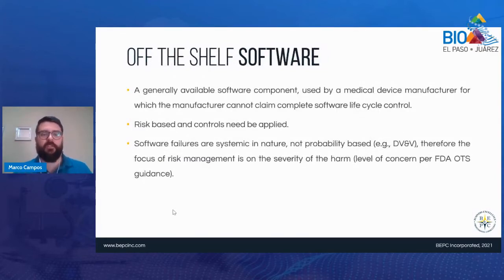One thing we would suggest is, as I said, we developed this quick video with an off-the-shelf platform, meaning it's a Microsoft-based platform, used on their technology. So if you're using off-the-shelf software, which FDA defines as a software component used by a medical device manufacturer for which the manufacturer cannot claim complete software lifecycle control, then you can start thinking about validating that software using the off-the-shelf software guideline by FDA. There are several things you will have to take into consideration to actually validate your software or application as off-the-shelf software.